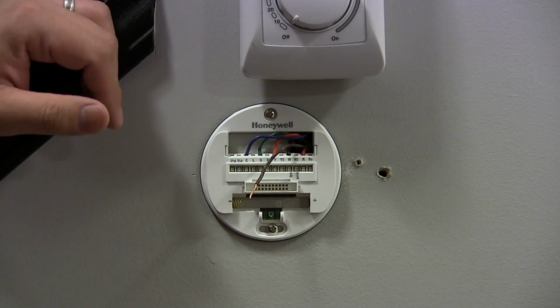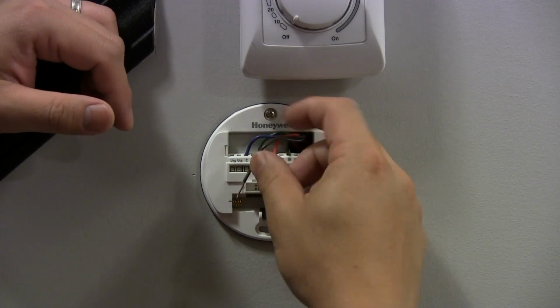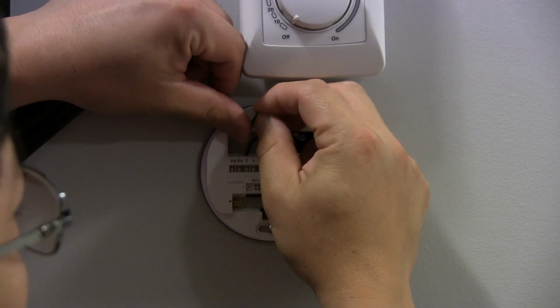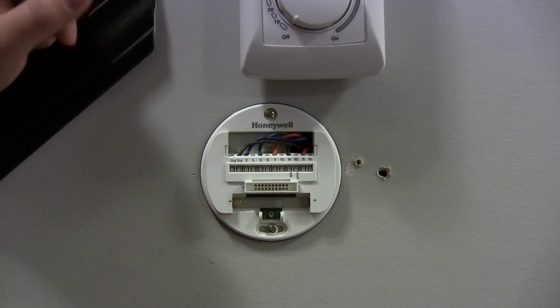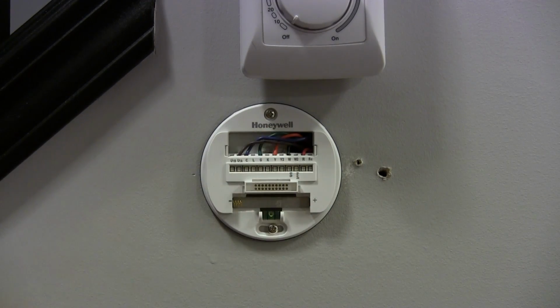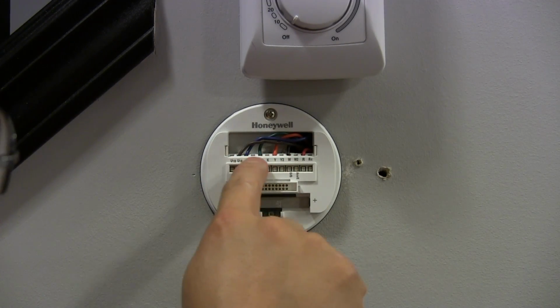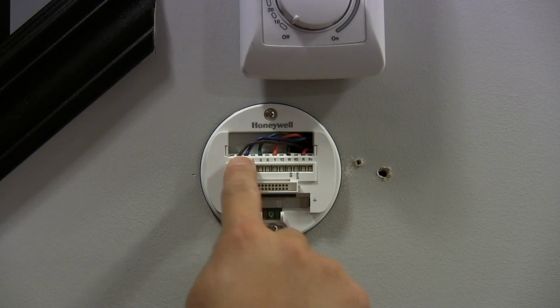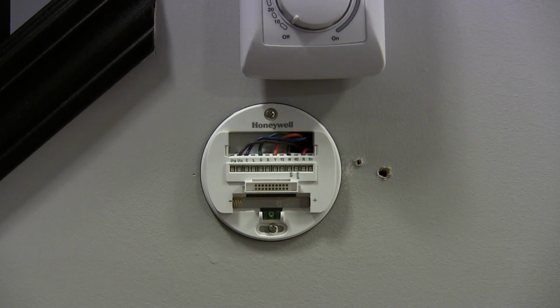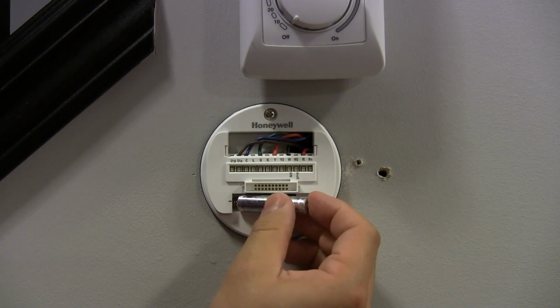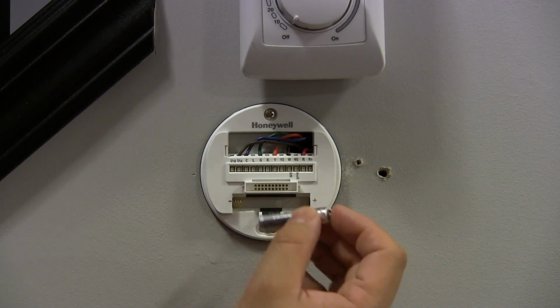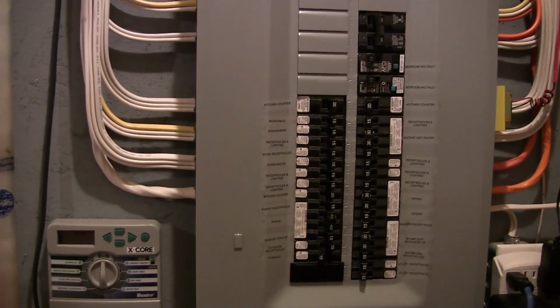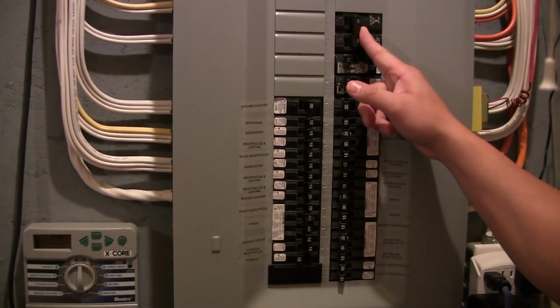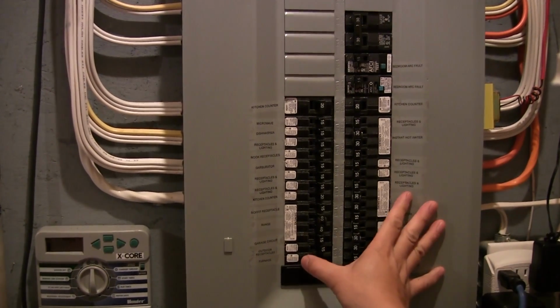In the context of how we're using it, it's fairly straightforward - we're just going to use U1A for our humidifier. Once everything's installed, we can carefully tuck all the wires back into the wall cavity, making sure there's no exposed copper along the pin bus, and that our thermostat is still level. Install the battery back in with the negative terminal towards the gold colored spring, then turn the power back on for the AC condenser as well as the furnace.